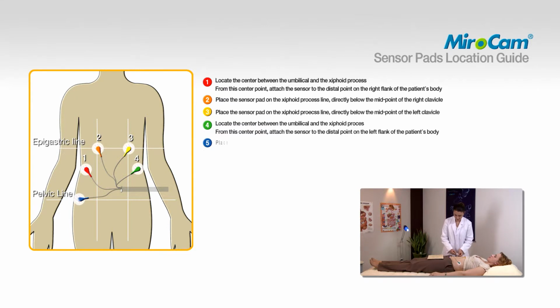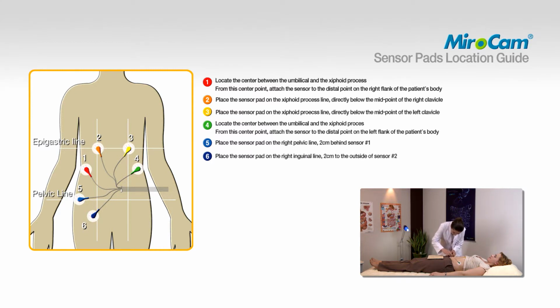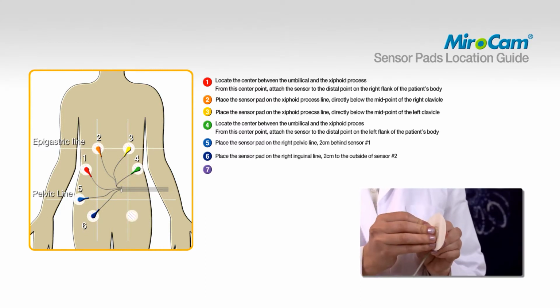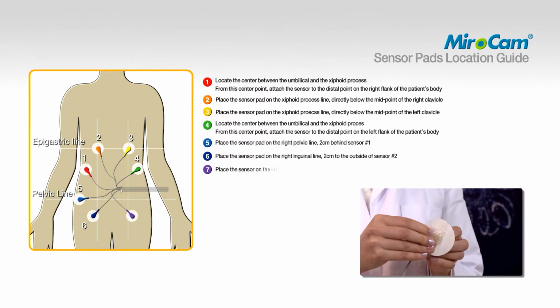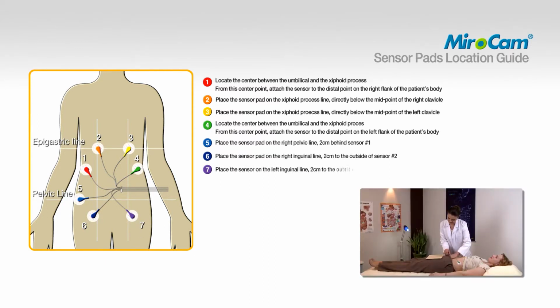To attach pad number 5, place the sensor pad on the right pelvic line, 2 centimeters behind sensor number 1. To attach pad number 6, place the sensor on the right inguinal line 2 centimeters to the outside of sensor number 2. To attach pad number 7, place the sensor on the left inguinal line 2 centimeters to the outside of sensor number 3.